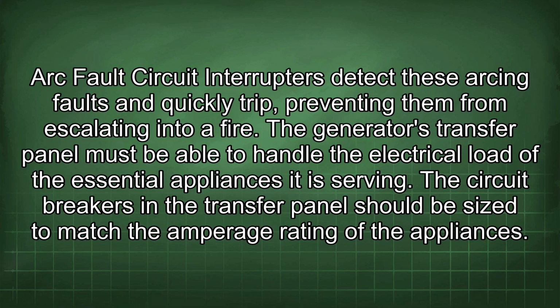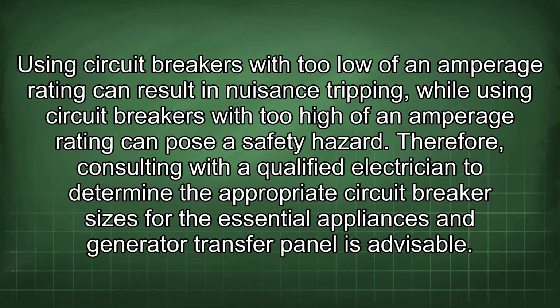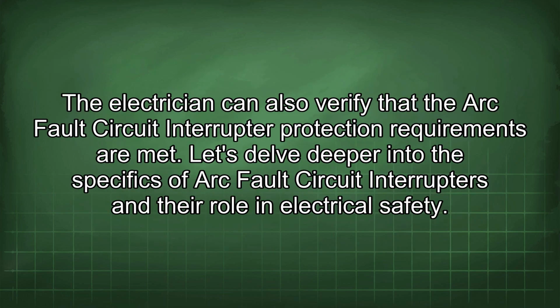The generator's transfer panel must be able to handle the electrical load of the essential appliances it is serving. The circuit breakers in the transfer panel should be sized to match the amperage rating of the appliances. Using circuit breakers with too low of an amperage rating can result in nuisance tripping, while using circuit breakers with too high of an amperage rating can pose a safety hazard. Therefore, consulting with a qualified electrician to determine the appropriate circuit breaker sizes for the essential appliances and generator transfer panel is advisable. The electrician can also verify that the arc fault circuit interrupter protection requirements are met.